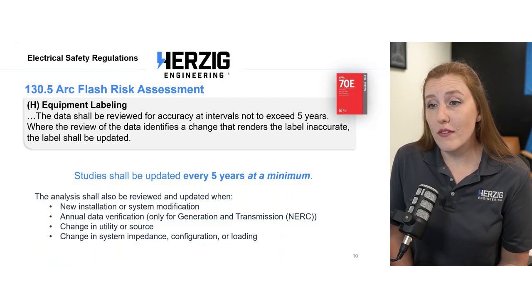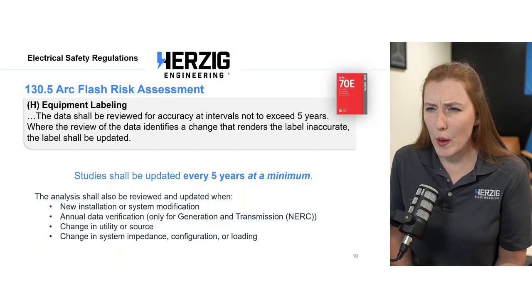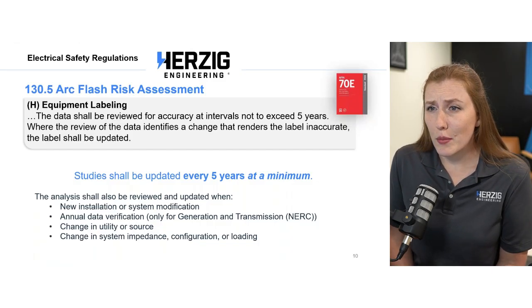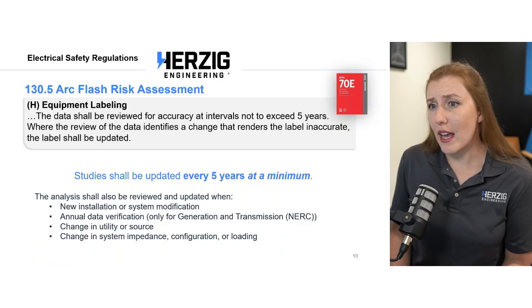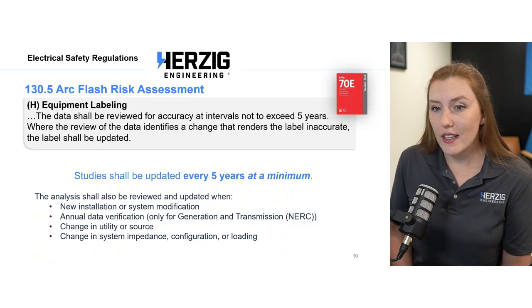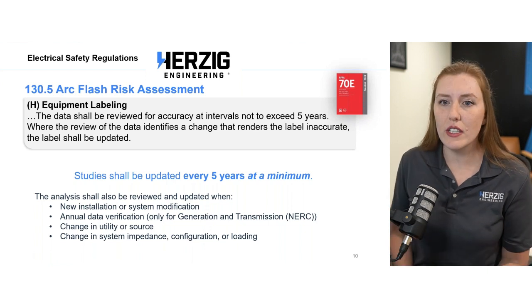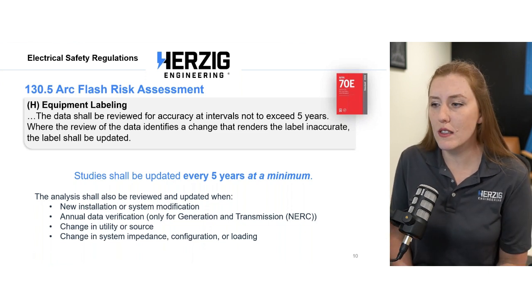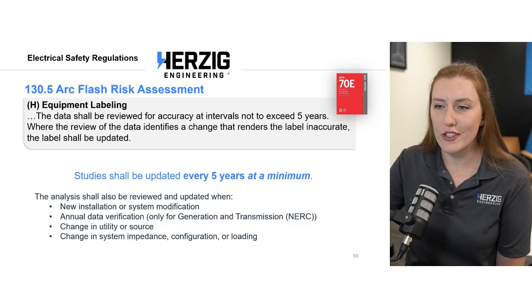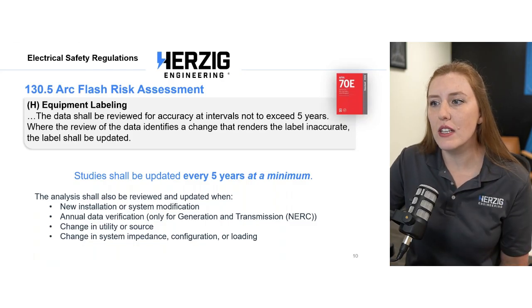Change in system impedance, configuration, or loading. So you've re-run equipment, you've added a new line, you've changed out the breaker types or the fuse types or whatever. Even things like that impact the study. Okay, so I'm just giving you an overall requirements look at arc flash analysis. So that's the stuff from the 70E.